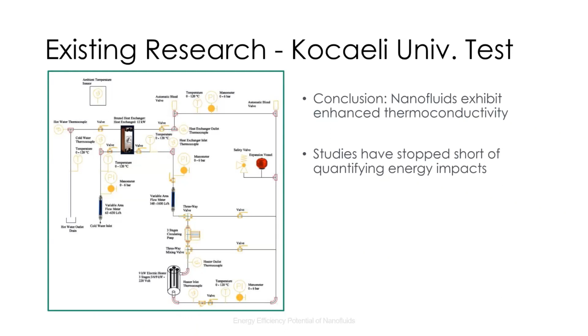towards the upper or middle portion of the diagram, and the heat transfer rates to the left-hand side of the heat exchanger were analyzed and compared using 100% water and then a 50-50 mix between water and HYDROMX, and the fluid flow rate on the right-hand side was kept constant. And this study concluded that the capacity for heat transfer through the heat exchanger was approximately 8% greater when using the HYDROMX solution compared to just water alone. However, the study did not quantify the energy impacts or implications of this nanofluid on heating or cooling systems.